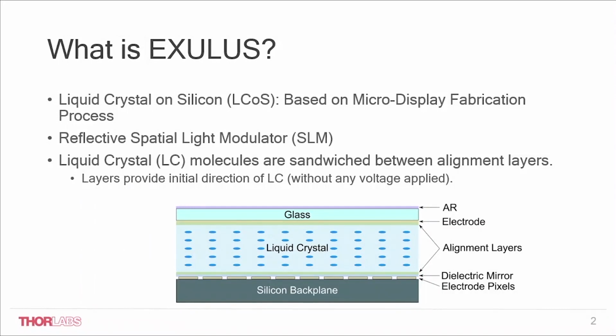The spatial light modulator, or SLM for short, is built upon the technology called liquid crystal on silicon, or LCOS. This is borrowed from the microdisplay fabrication process, which is by itself a very mature process. For example, you can find microdisplays in overhead projectors for conference presentations or in movie theaters. Our SLM panels are reflective type, which means that when you use it, the light source is incident normally on the SLM panel and is reflected backward.